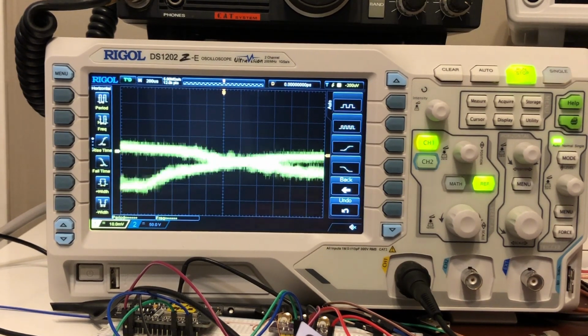Today we're starting off with chapter 3, to set the horizontal system. And that includes delayed sweep and time base mode. So, delayed sweep can be used to enlarge a length of a waveform horizontally to view waveform details.